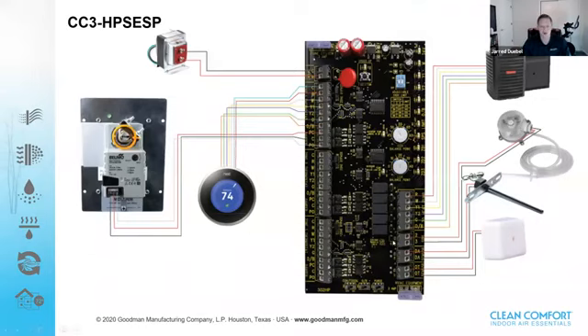So this is more of a close-up of what that panel is going to look like. First of all, again, you're going to get that transformer in the kit. We always recommend installing the zone control system on its own isolated transformer, so you don't run into a position where, if you're power stealing from another transformer, you might overload it, which as we all know can start to have a system act a little wonky. So hot and common here, we're going to power up that zone control system. And then zone control thermostats are going to be here on the left-hand side of the panel. And then each correlating zone damper is going to be right there on that same terminal strip.